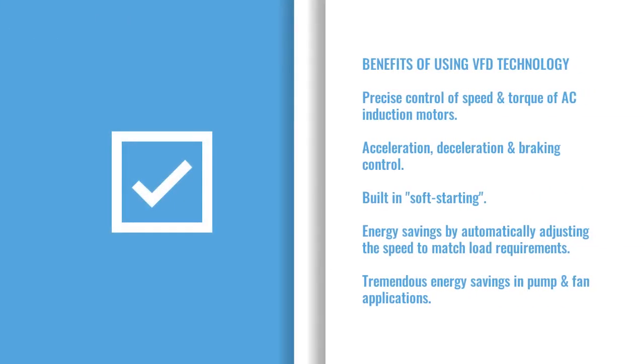Benefits of VFDs include precise control of speed and torque of AC induction motors, including acceleration, deceleration, and braking control. VFDs also provide built-in soft starting and energy savings by automatically adjusting the speed to match load requirements, with tremendous energy savings in pump and fan applications.